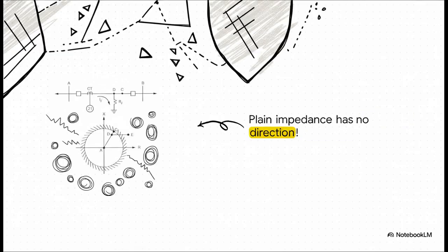Back in the early days of power protection, engineers used literally the simplest shape possible, a plain circle centered right on the origin of the graph. If the impedance dropped anywhere inside this circle, the relay tripped. Simple, right? It was a really great start, and it provided a solid zone of protection. But if you look closely, there's a major geometrical flaw with this design.